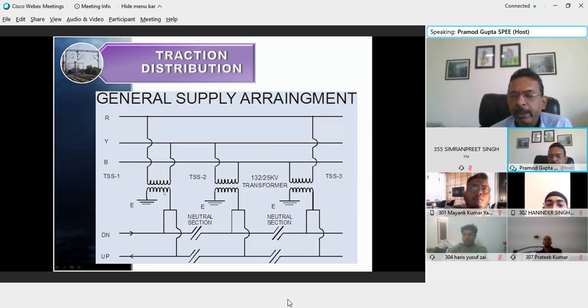The primary requirement is the voltage drop at the other end of the system. Normally we have a feeding zone of 60 kilometers, which is 30 kilometers on either side of the TSS. It means the TSS is situated in the middle of its feeding zone, feeding 30 kilometers on one side and 30 kilometers on the other side.